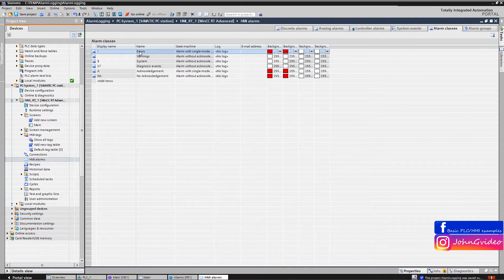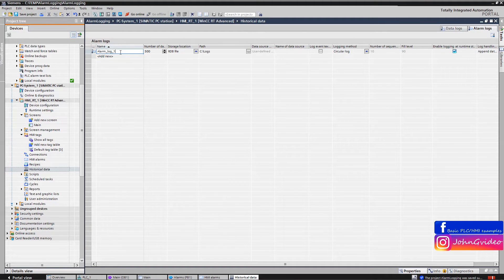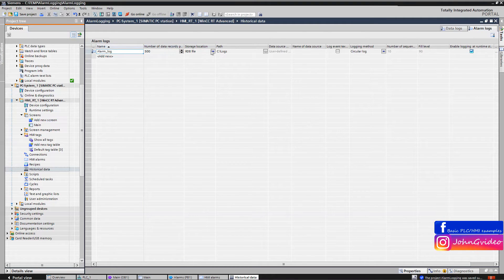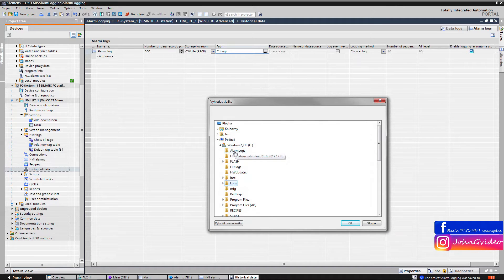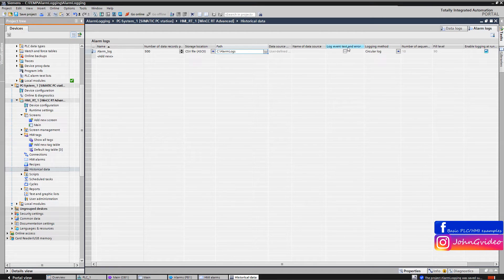We use the Errors alarm class for our created discrete alarms. Now we go to the historical data option, and in the alarm logs window we create a new alarm log with the name 'alarm log'. We use 500 data records. As the storage location we use a CSV file. We change the path where we want to save this alarm log to the alarm logs folder, and we also need to log event text and error location by checking the checkbox. We use circular logging for these alarms.